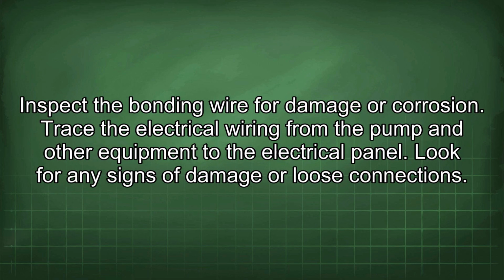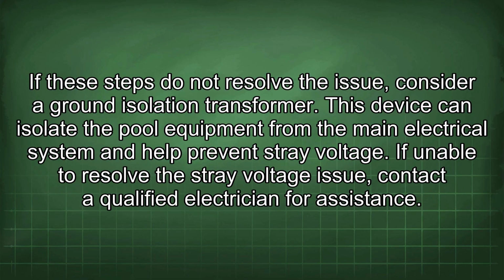Inspect the bonding wire for damage or corrosion. Trace the electrical wiring from the pump and other equipment to the electrical panel. Look for any signs of damage or loose connections. If these steps do not resolve the issue, consider a ground isolation transformer. This device can isolate the pool equipment from the main electrical system and help prevent stray voltage. If unable to resolve the stray voltage issue, contact a qualified electrician for assistance.